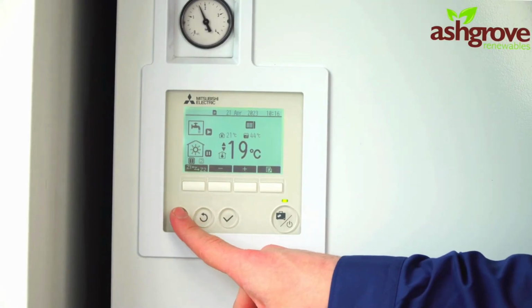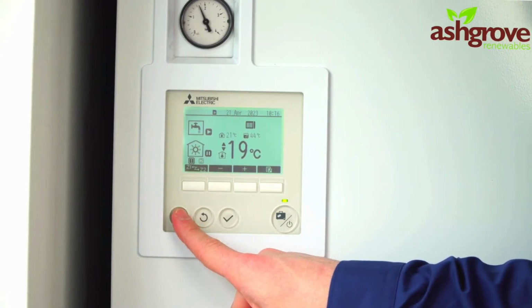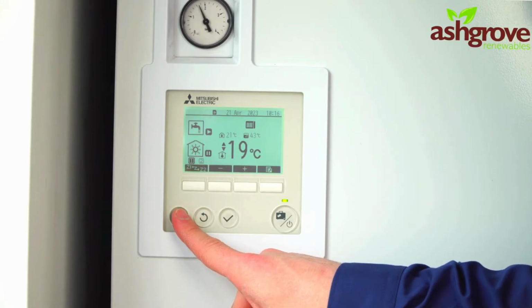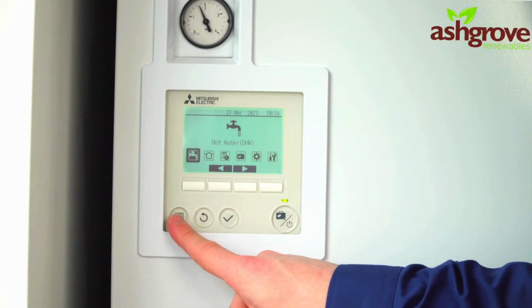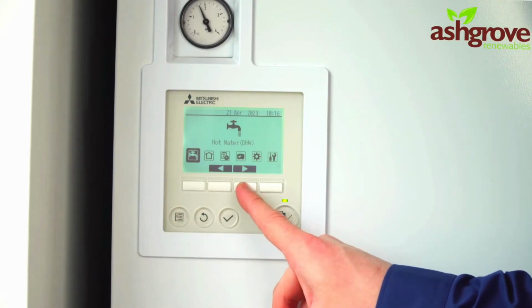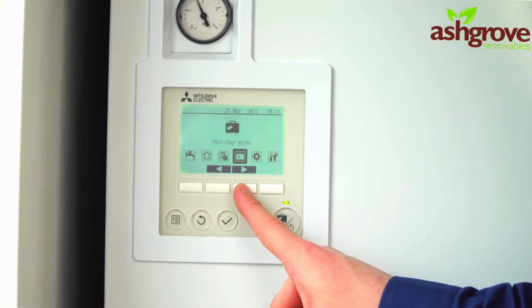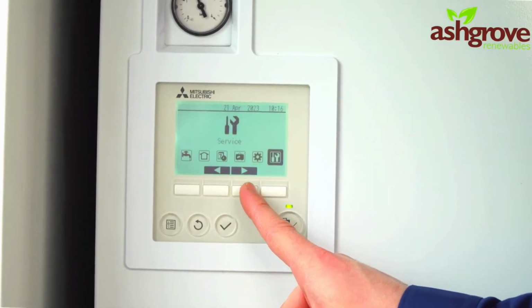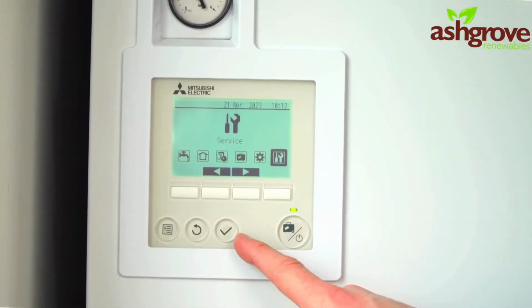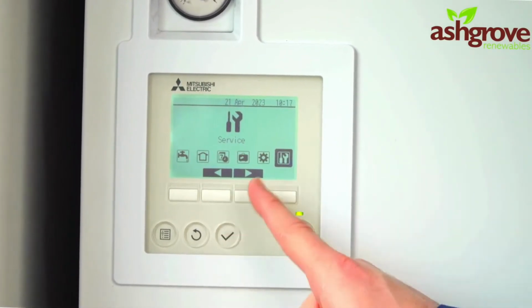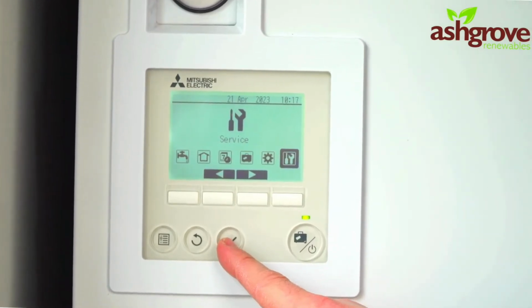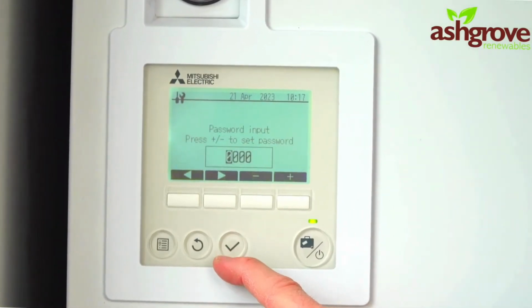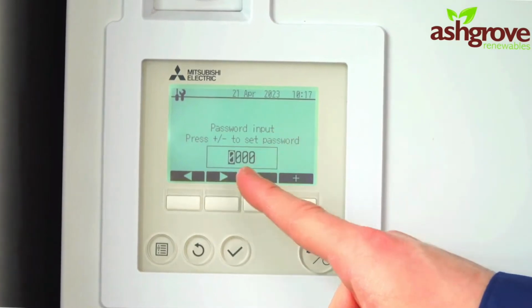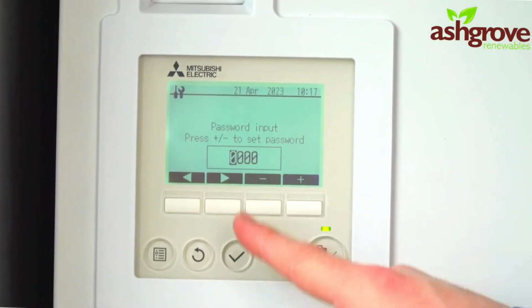On first installation, it's good practice to run both pumps and 3-port valve to test before starting the unit. Simply press the menu button once, scroll all the way across using the right arrow, and you will find the service menu with the spanner and the screwdriver. Press the tick to access it. The password is a default 0000, so simply press the tick.